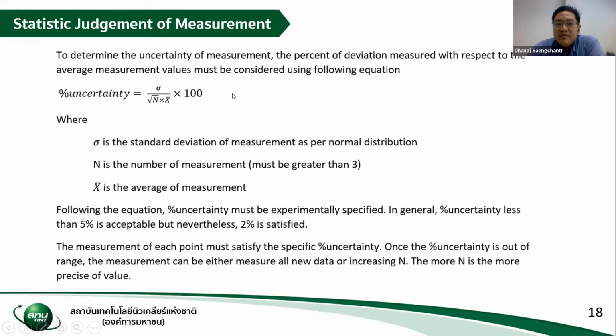So we have to determine what is good for that measurement. With this equation we developed from the standard deviation and the standard deviation to mean ratio, we have to make some criteria. For example, if you measure 3 times, then you can have your average measurement. And with this average measurement, you have to see the standard deviation of your data. And with this percentage, we require that this must be less than 5% at each measurement point. But actually we prefer less than 2% standard uncertainty, which will satisfy our measurement.